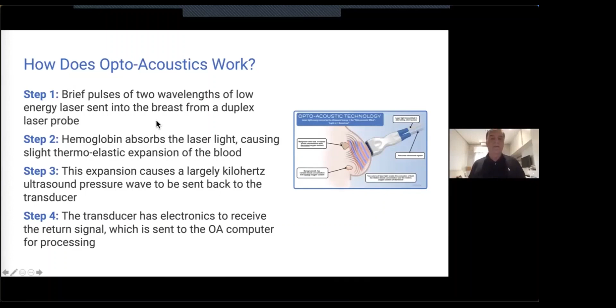This is done at very low frequencies. So say we're doing breast ultrasound with a 5 to 16 or 5 to 18 megahertz transducer. We can just expand the bandwidth at the lower end. So we go all the way from 1 megahertz up to 18 megahertz. And then we can pick up the pressure waves coming back, which are at lower frequency than we usually do breast ultrasound at.